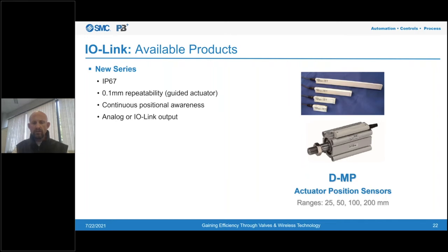This product series allows us to capture real-time position information from a pneumatic actuator. Traditional auto switches typically capture information at a particular set point on the actuator stroke, sending an output to the PLC so it can issue another command. With this actuator position sensor, we're able to read where the actuator is at any point in its stroke.